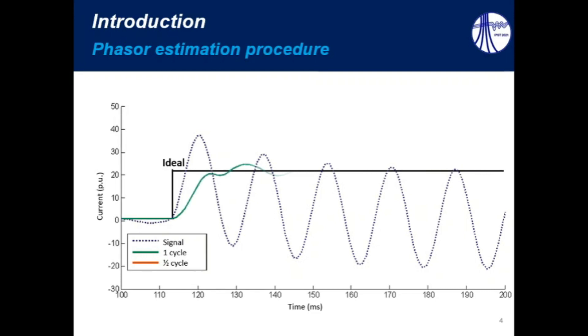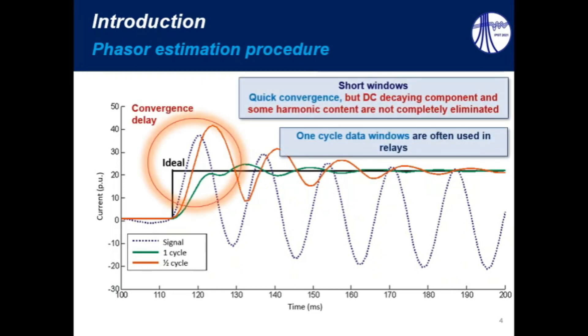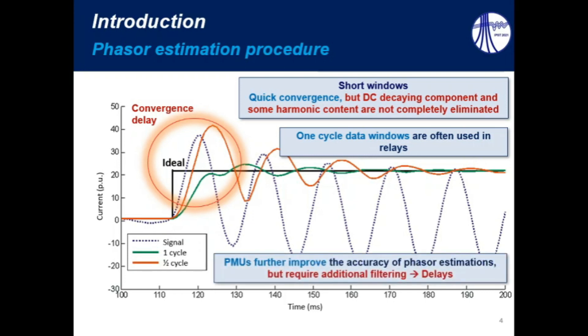However, in real life, when we apply different algorithms, which use one-cycle data or half-cycle data, we can see that the transient response is different for each algorithm. Regarding the convergence delay, we can see that when we use short windows, a quick convergence is verified, but the decaying components and some harmonic content are not completely eliminated. Thereby, one-cycle data windows are often used in protective relays, but we know also that PMUs further improve these algorithms, providing even more accurate phasor estimation.